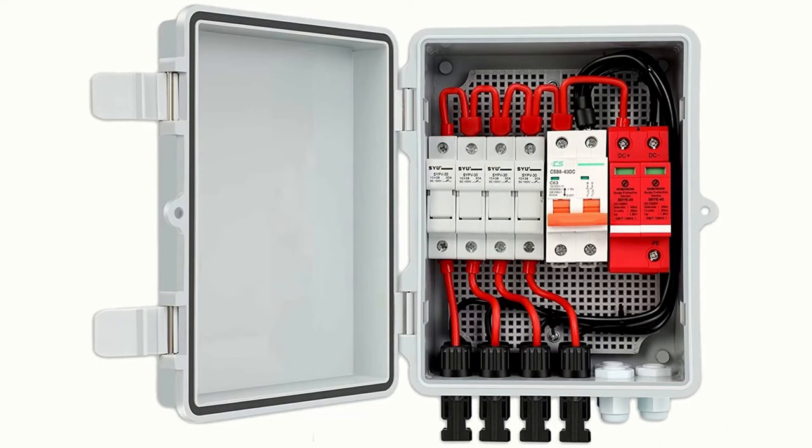Depending on the system design, the fuses or circuit breakers can be installed directly inside the combiner box itself. But it's important to verify the temperature ratings and other specifications of the overcurrent protection device since it may be subjected to high temperatures. Otherwise, the circuit may experience nuisance trips or blown fuses during hot weather. This video won't explore the details of when to fuse the positive or negative lines as that becomes a bit more advanced based on the panel inverter and system design, but you'll typically only fuse the ungrounded or hot wires when working with a standard inverter.